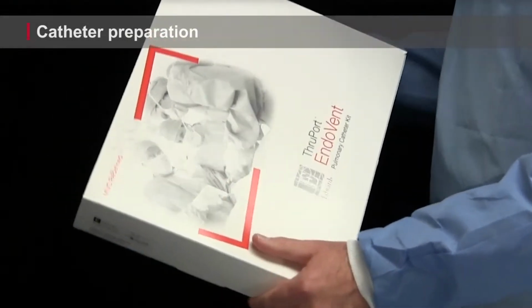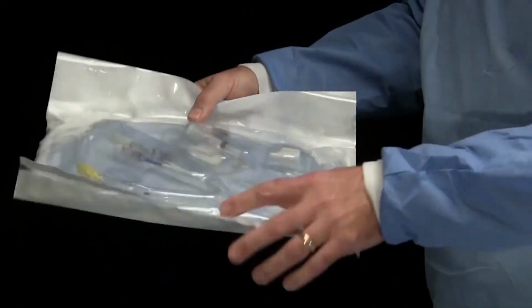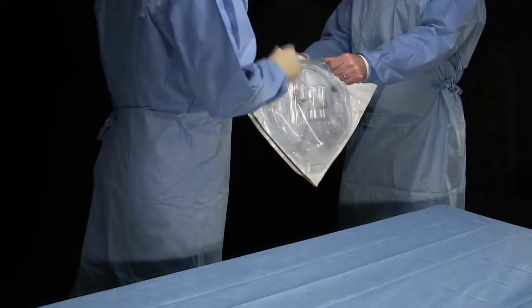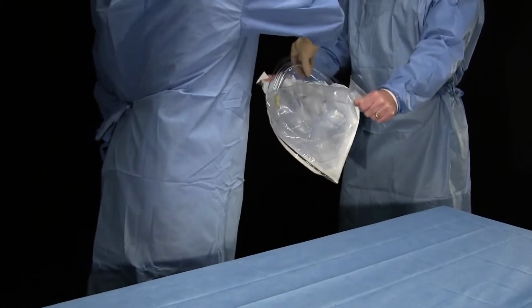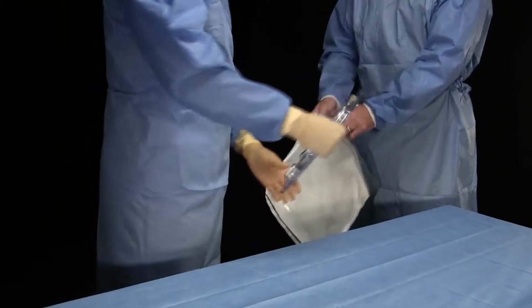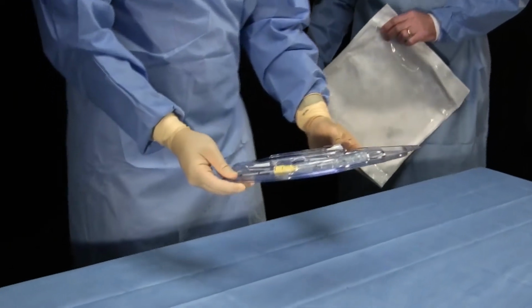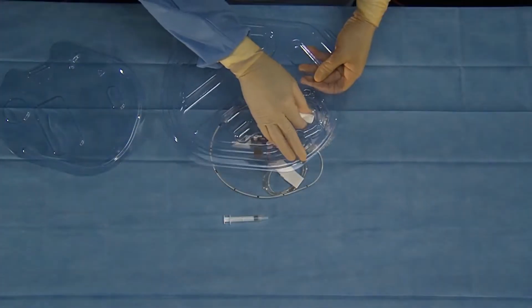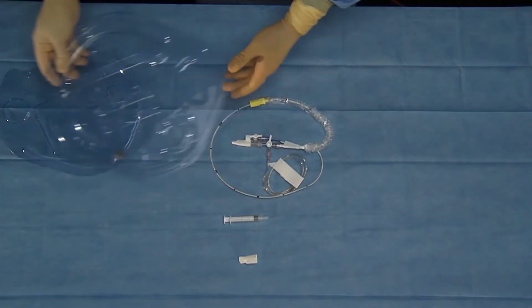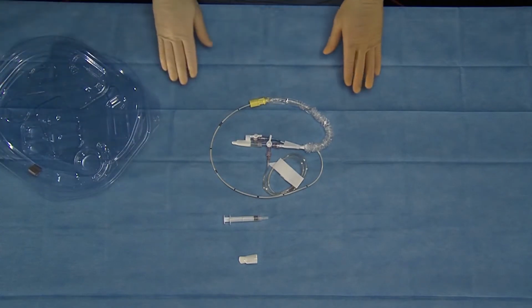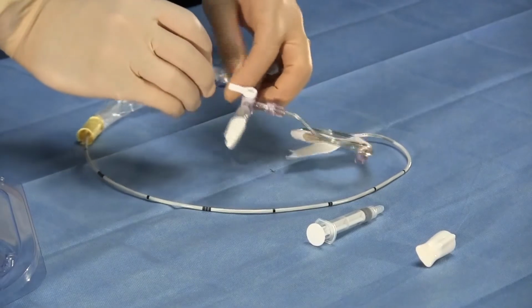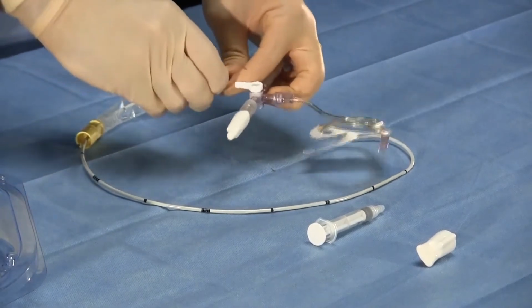Upon removal from the box, visually examine the sterile packaging for evidence of damage. If any damage is observed, do not use the device. Remove the EndoVent catheter and all components from the package and place on the sterile prep table. Visually inspect all the components for damage. If there are any signs of damage, do not use the device. Tighten the pre-assembled luer connections. To prep this device, perform the following steps.